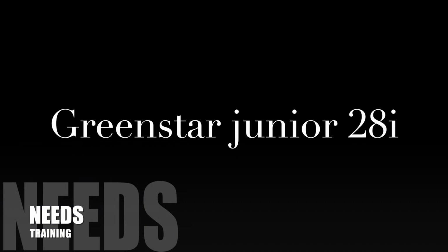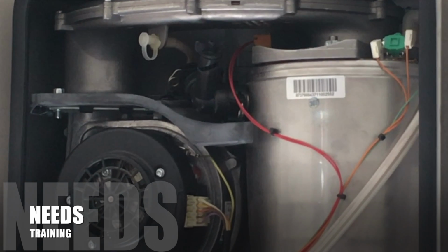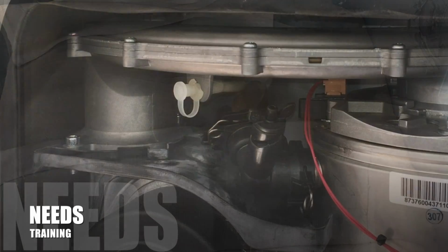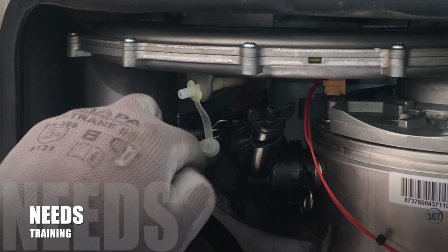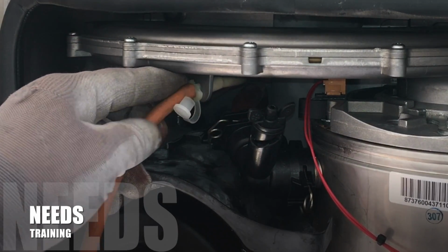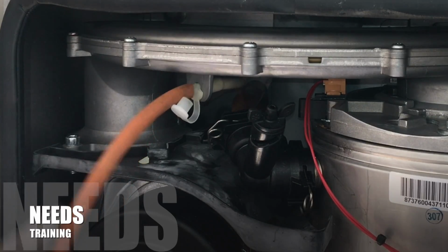Video was made with manufacturer's advice and best practices. Before you work on the appliance, make sure that the working area is well protected, and ask the customer if there are any problems with the appliance. Firstly, a fan pressure test will determine if you need to remove the baffles to clean the heat cell.